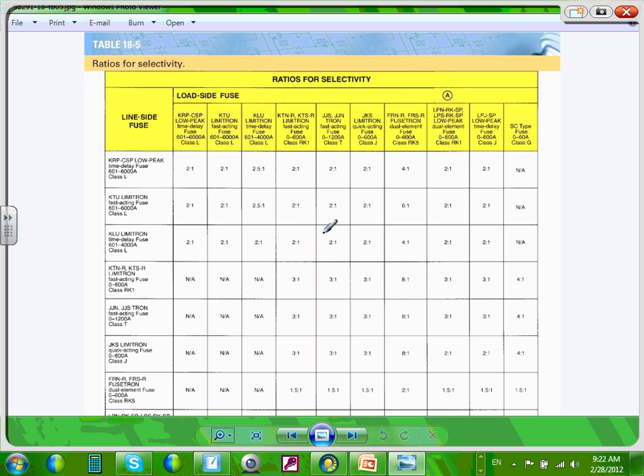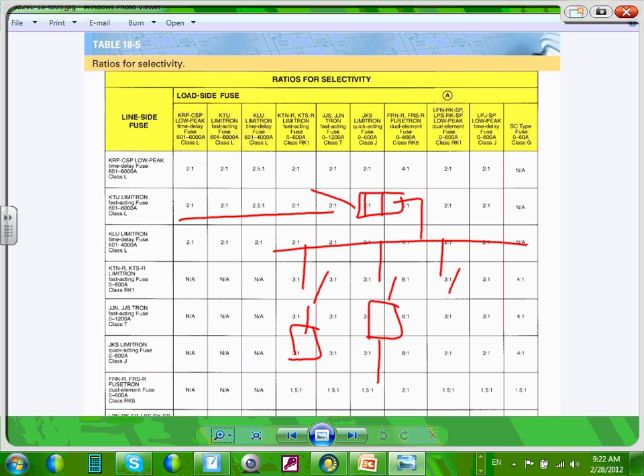So for the most part, I have a fuse, and this fuse is feeding a panel, and here's my fuse here, and my other fuse is here, right? For the most part, if this fuse is 400 amp, and none of these fuses is higher than half of the 400, what's half of 400? 200. There's a 200 amp, 100 amp, 150 amp. If the highest one is half of the main, you're almost guaranteed full coordination. Which means the main is twice the largest feeder. The main is twice the largest feeder.